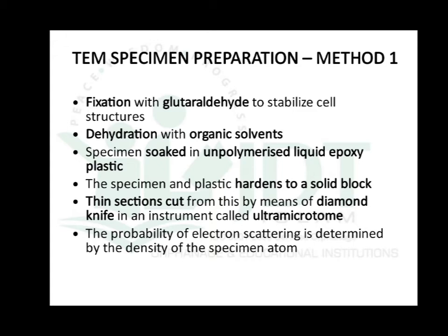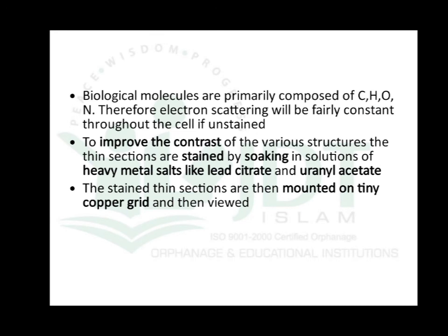The probability of electron scattering is determined mainly by the density of the specimen atoms. Biological molecules are primarily composed of carbon, hydrogen, oxygen, and nitrogen, so electron scattering will be fairly constant throughout the cell if unstained. To improve contrast, the thin sections are stained by soaking in heavy metal salts like lead citrate and uranyl acetate. The stained sections are then mounted on tiny copper grids for support and viewed under TEM.